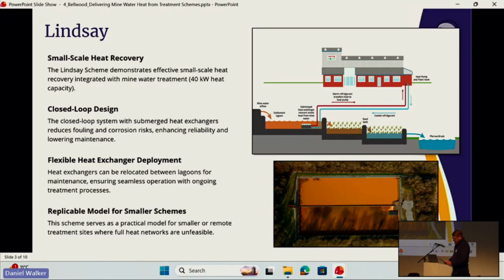2 energy blade heat exchangers sit submerged in the lagoon, but above the level of any ochre. The blades recover heat while still allowing the flow to move around them. The recovered heat is then transferred through pipework to a nearby building where a heat pump lifts the temperature for space heating. This design allows for the energy blades to be moved between lagoons during lagoon maintenance periods, so treatment can always keep running.